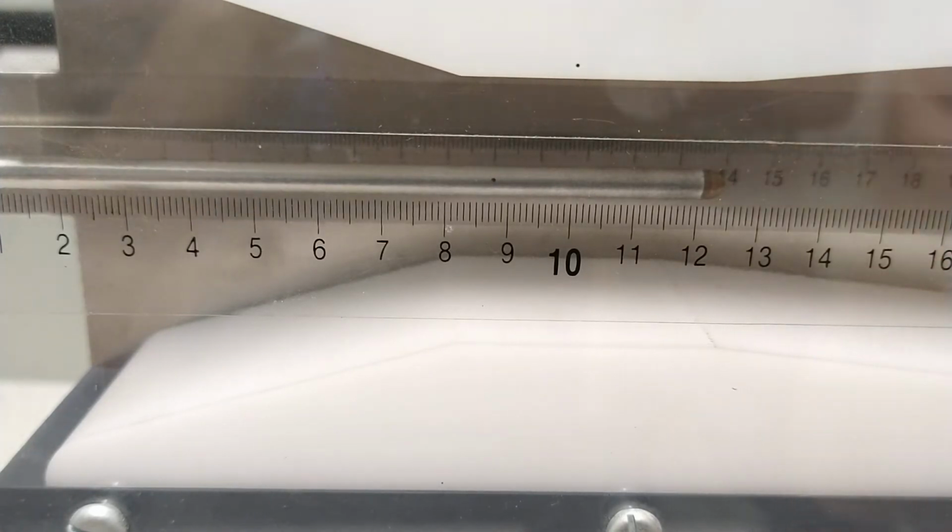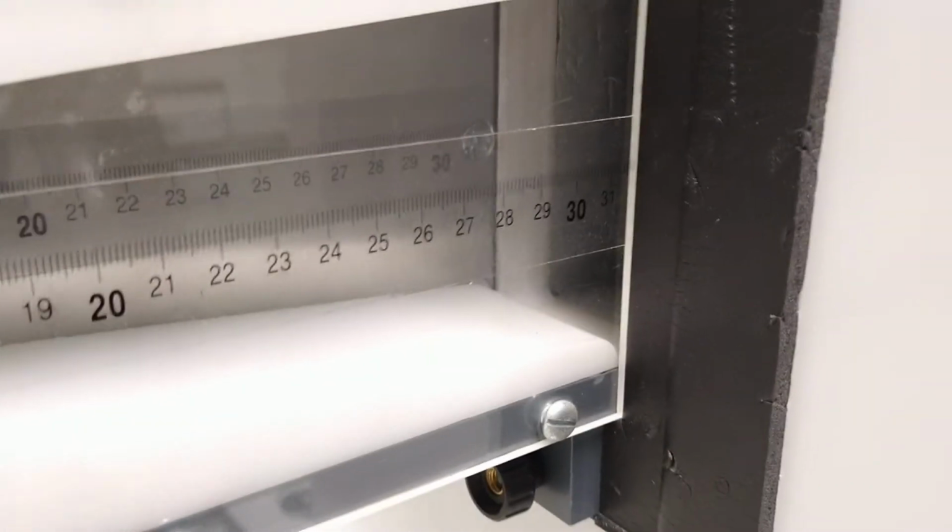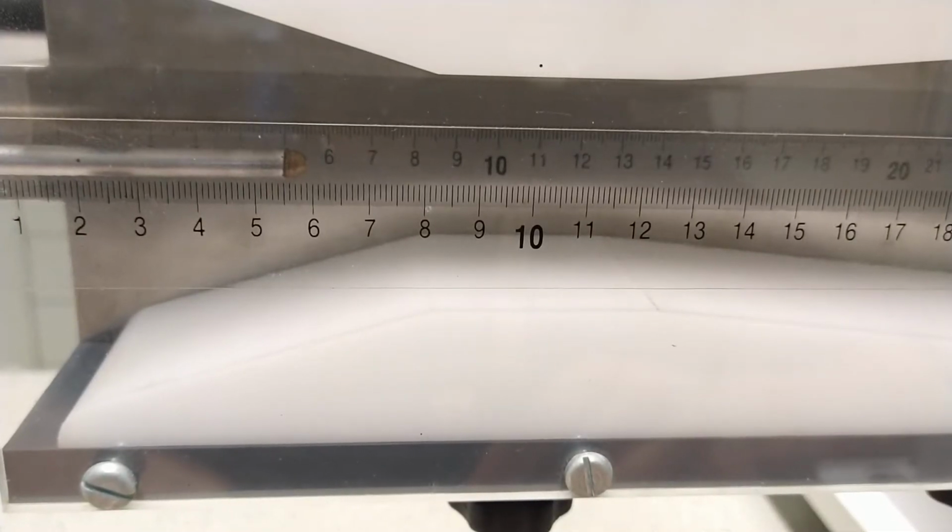You can use those to demonstrate Bernoulli's principle, which says that at any point in the laminar airflow, the sum of the velocity pressure and the static pressure should be a constant. As we move this to various locations along the Venturi, you'll see that the velocity pressure varies wildly, but the sum of the velocity pressure and the static pressure remains more or less constant. There are some effects as it starts to exit into the atmosphere here, and some effects where it's coming from the plenum chamber over there. But that's the basic idea.